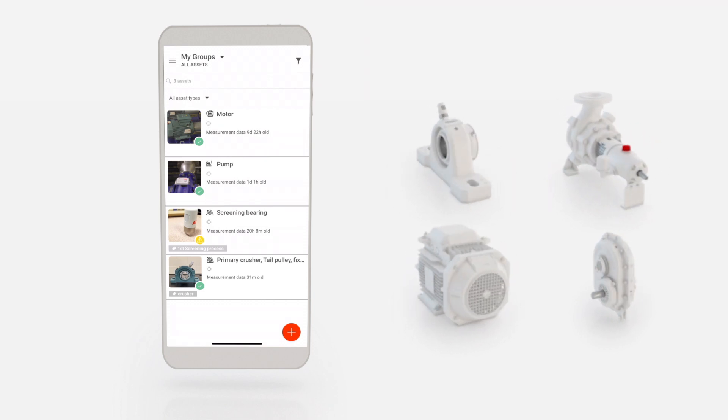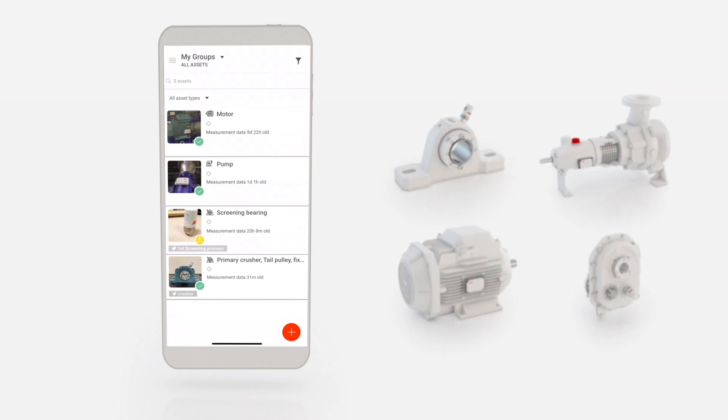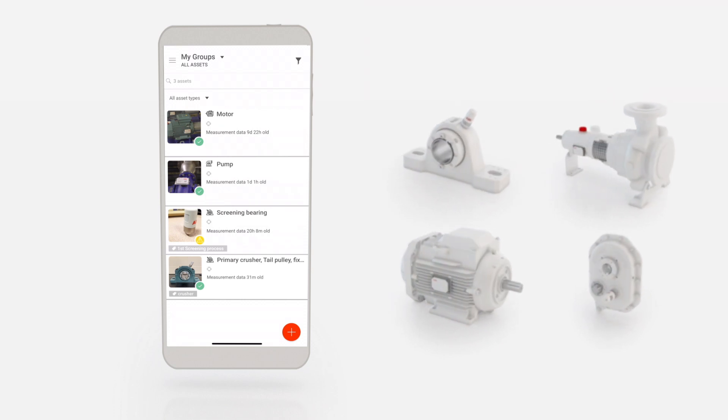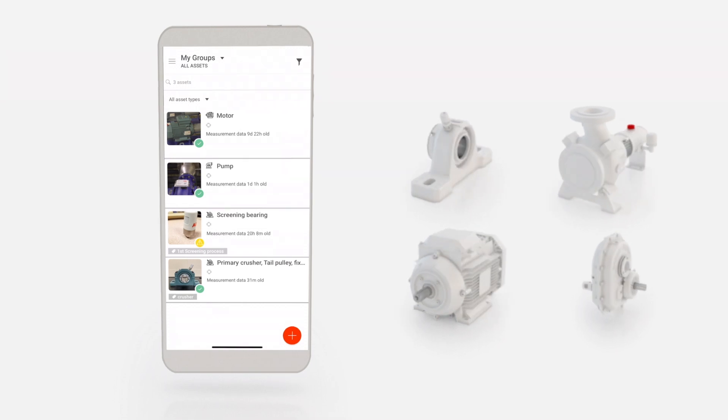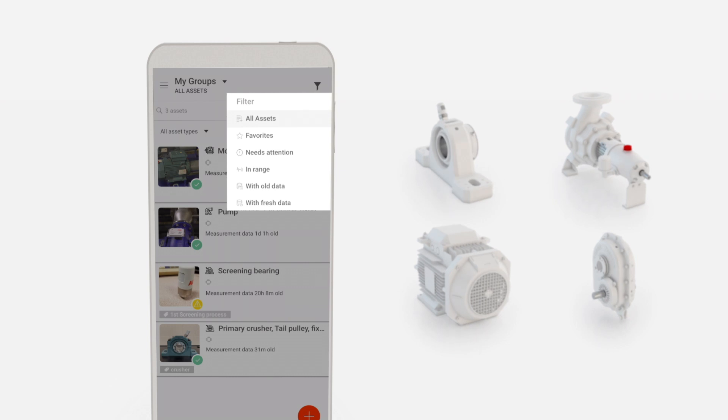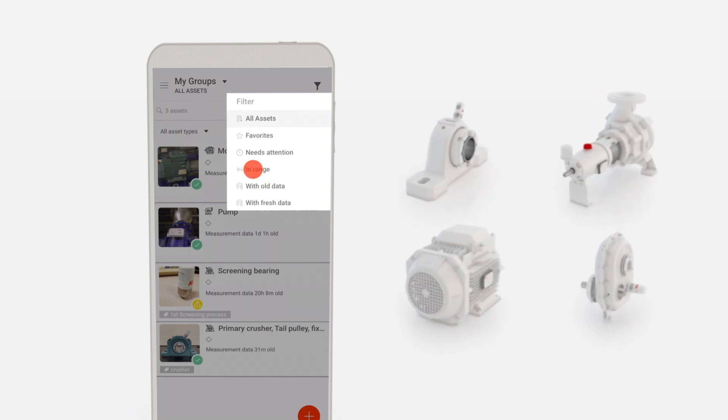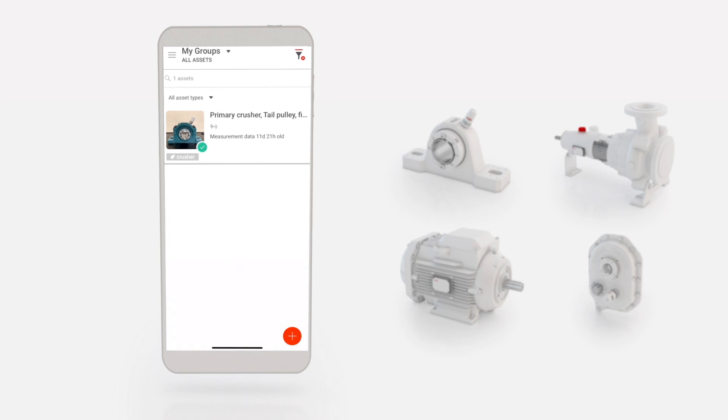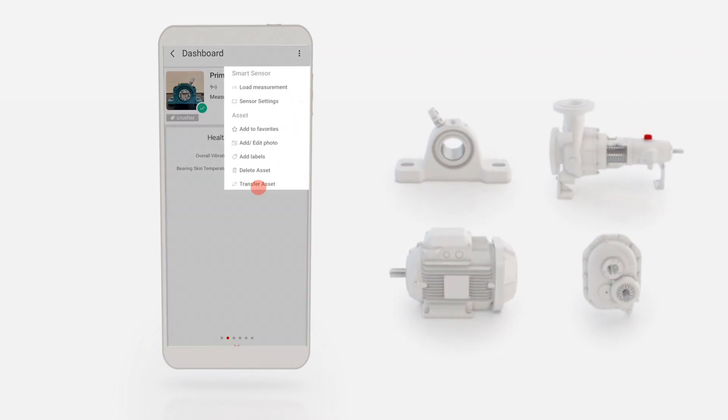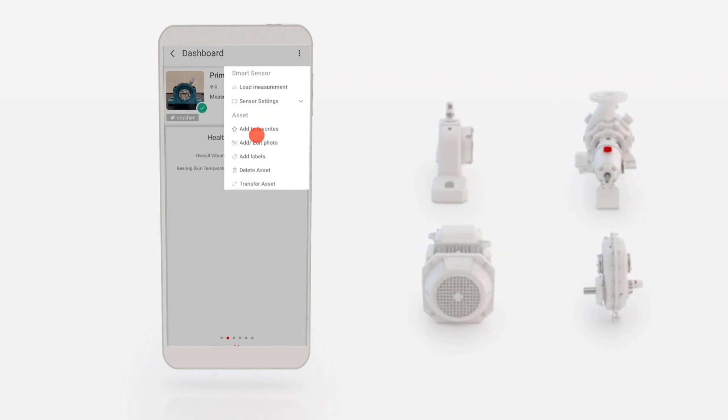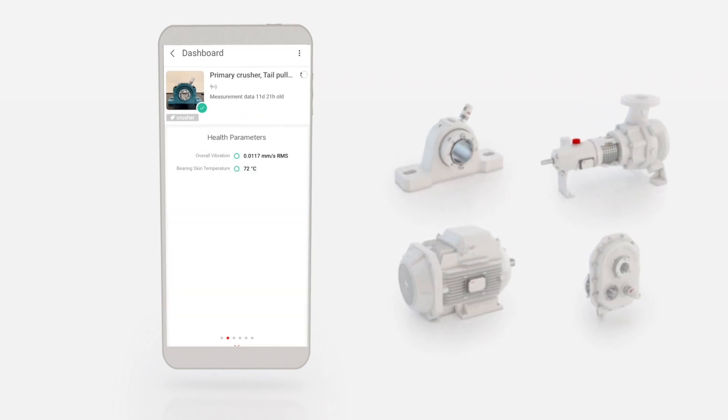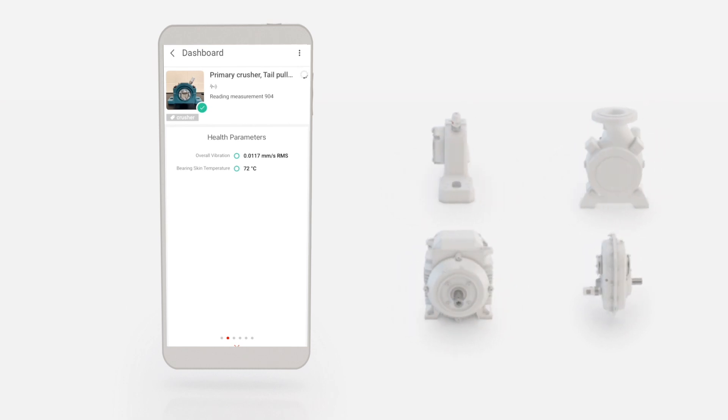Data measurements can be manually collected by filtering assets that are in range. Tap the Filter icon in the top-right corner and select In Range to display all sensors that are in range. Tap on the desired asset. Tap the Menu icon in the top-right corner and select Load Measurement. The data collected by any user is then synchronized to ABB Ability.